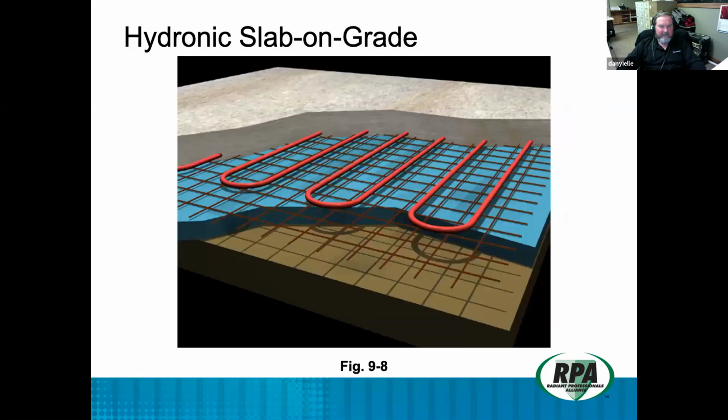In the case of doing radiant slabs, you absolutely have to have the insulation below the slab itself. The other thing, if you're going to do radiant cooling, is you have to be able to dictate what the final finished surface is going to be. Our office here is basically polished concrete floors. Our preference in a residential application would be a hard stone or a hard tile surface. What you cannot use is hardwood floors.